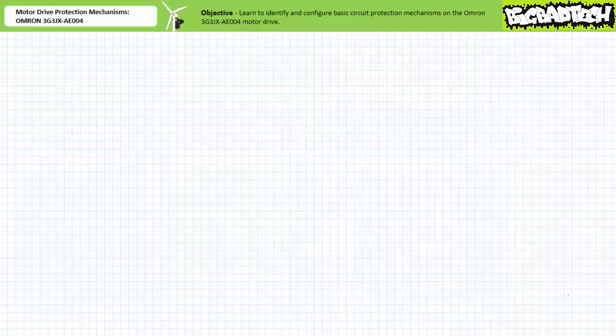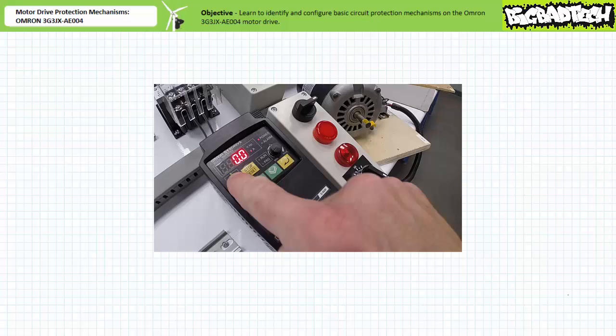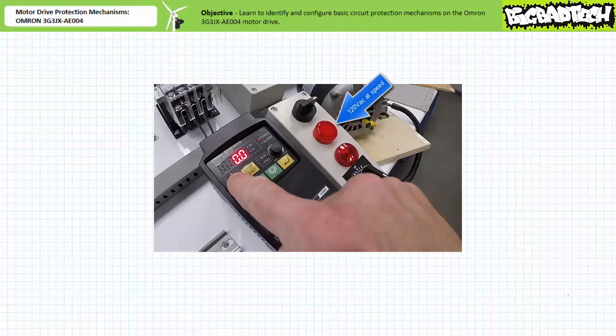If we unintentionally set the overload limit too low, we might never break over to constant speed mode and just hover in limbo indefinitely. Note two indicator outputs have been enabled: a 24V DC pilot lamp on the bottom, low side switched by multifunction digital output P1 executing the run function; and a 120V AC rated pilot lamp on the top, high side switched by the multifunction electromechanical relay output executing the constant speed arrival function. Recall with active overload limitation at the default 3.9 amps, it took 10 seconds to accelerate to base frequency. Let's see how it responds with the overload limit at a comically low 1.62 amps.